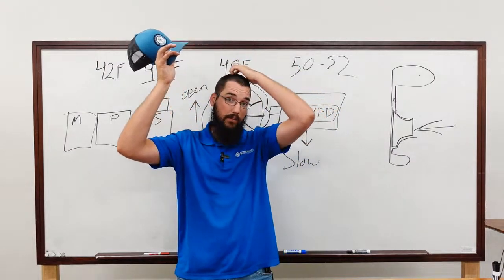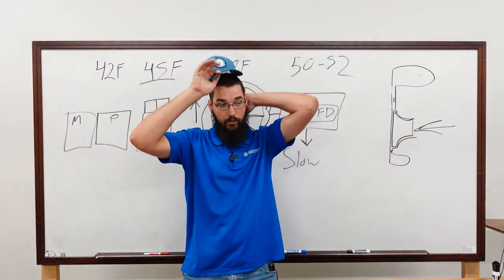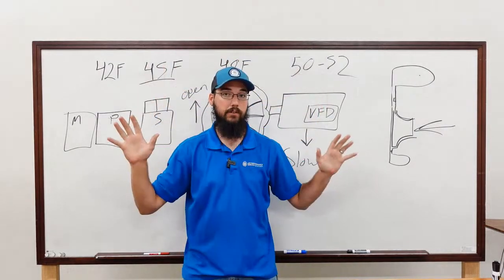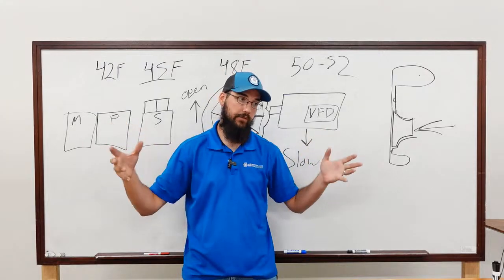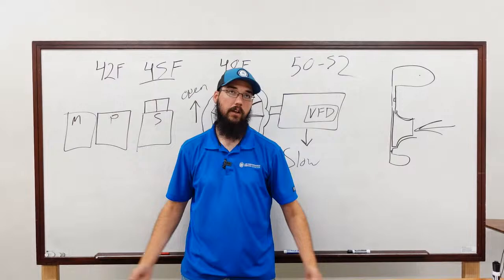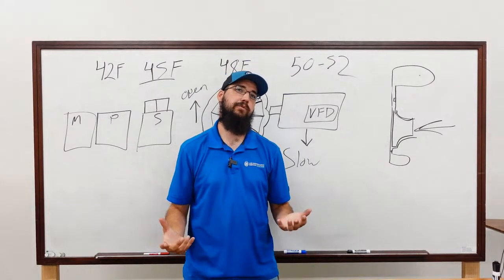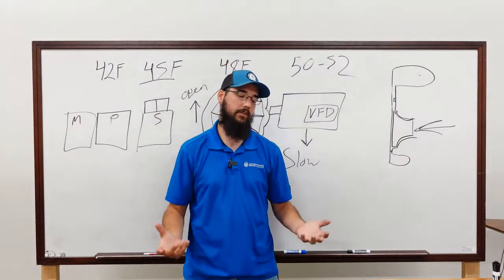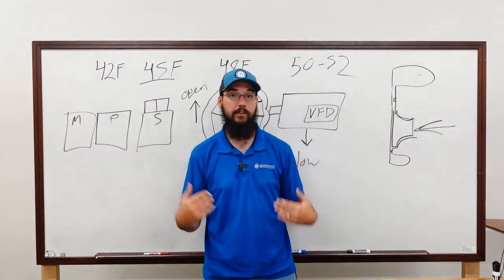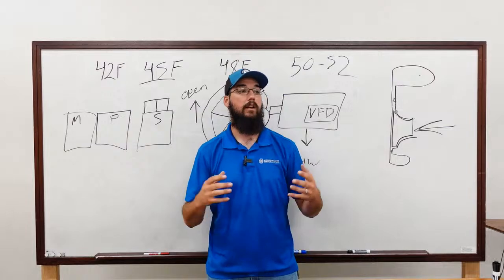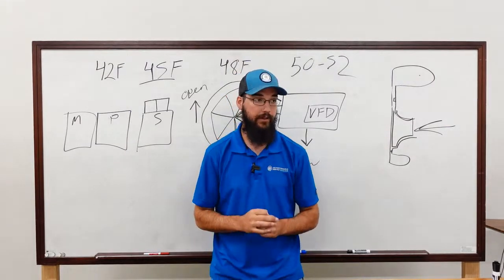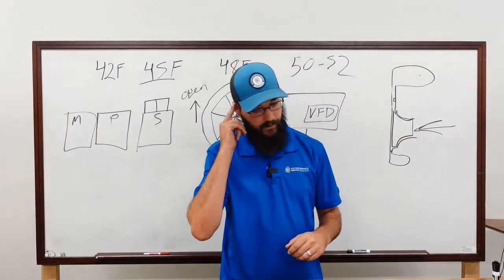And if you've got a DX barrel, meaning the refrigerant's inside the tubes, it's not, in my opinion, and some people disagree with me, as big of a deal. Because if the water freezes, it's freezing on the outside of the tube and it's got plenty of room to expand. And not that much refrigerant sits in those tubes to begin with. You have refrigerant in there, but it's not like a flooded barrel where literally the entire barrel is full of liquid refrigerant. And you've got a small amount of water in tiny little tubes, which isn't that hard to freeze.